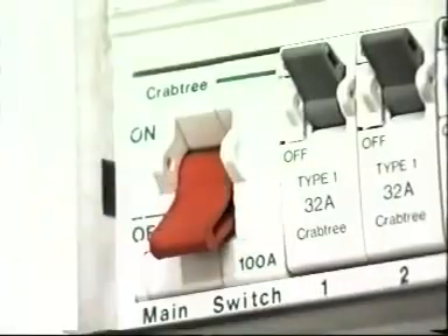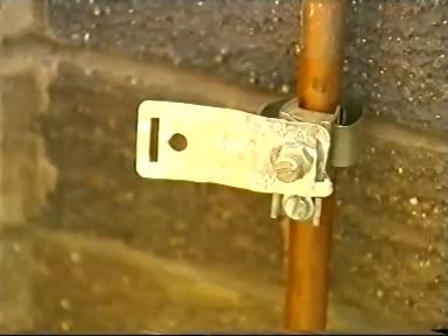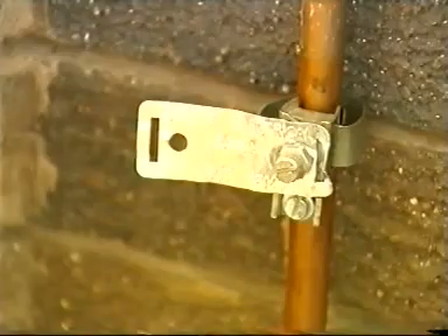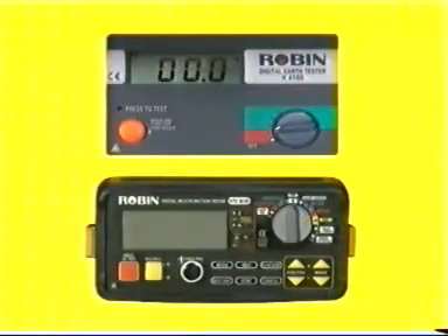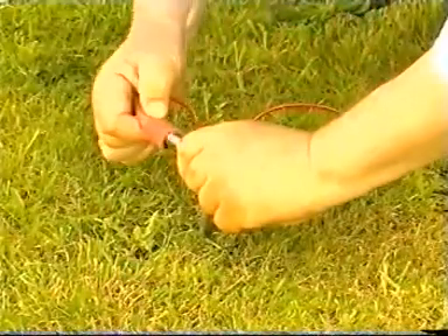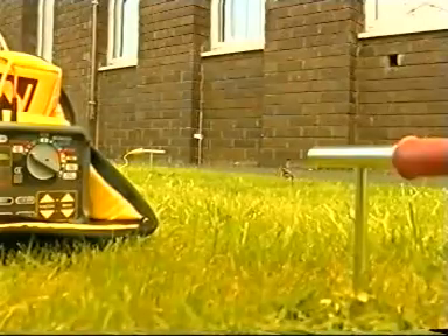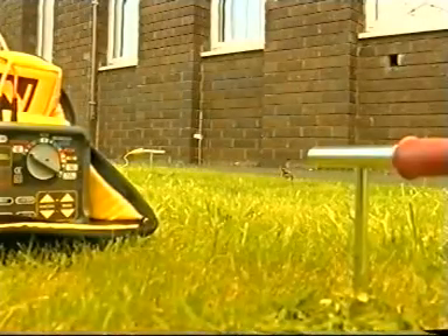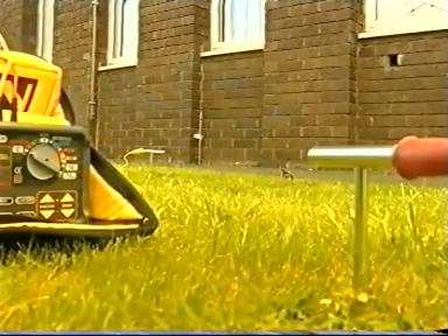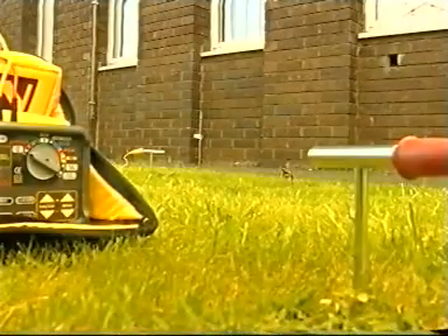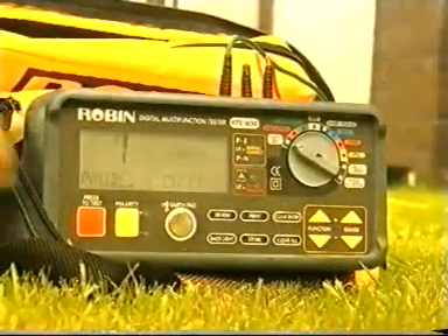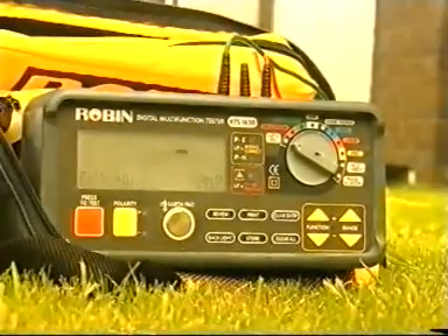Before testing, the supply to the installation must be isolated and the electrode disconnected from the consumer's main earthing terminal. Using a dedicated earth resistance tester or multifunction tester having this facility, 2 temporary earth spikes are driven into the ground at the distances specified in the instruction manual of the test equipment. To ensure resistance areas do not overlap, 3 readings are taken following movement of the potential electrode.